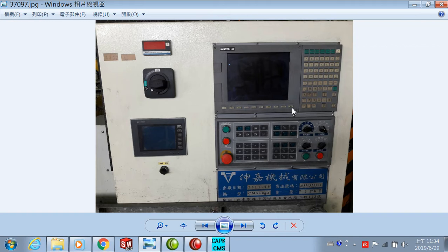This production line was manufactured by the Japanese 30 years ago. In this grinding station, the Japanese allowed the Taiwanese to set 20. Every 20 grindings, the grinder will refine once.